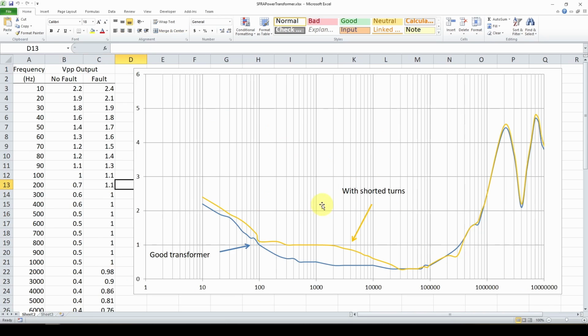Here is the same test, but instead of using the switching transformer, I used my 117 volt to 12 volt power transformer. You can see the SFRA test looks kind of similar with and without shorted turns. And up at the high frequencies, we get a big spike in the impedance as we get a resonance with the L and C.